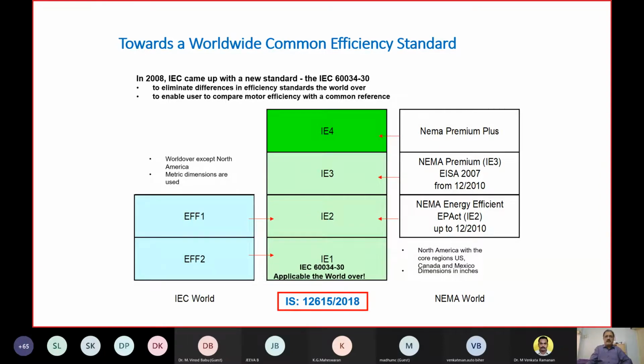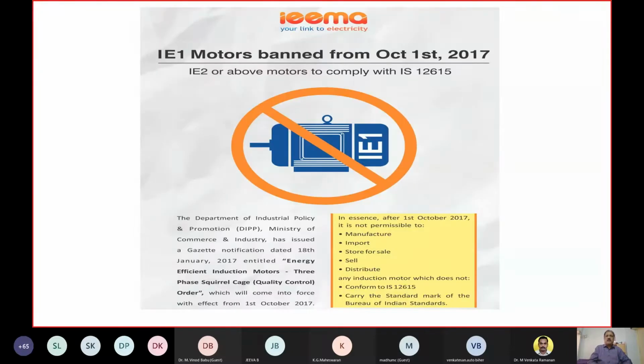So in India, we adopted this IEC 60034-30 as IS 12615 2011. The original standard in IEC came in 2008. We were behind by 3 years, and in 2011 we adopted IE standards in India. In 2018, including an IE4 efficiency and dropping IE1, India has now efficiency standards for IE2, IE3, IE4. So any one of you interested in further implementations or choice of recommending or advising any of your industry clients, or you would like to undertake some case studies on IE technologies adopted by the IEC, we can give you more inputs on that.